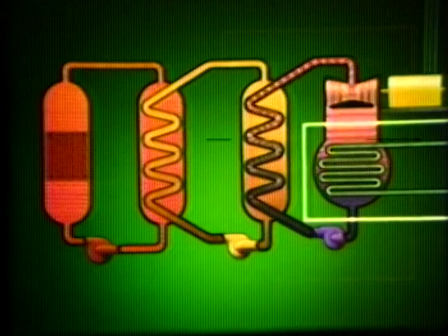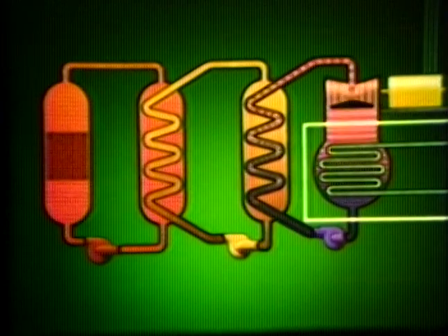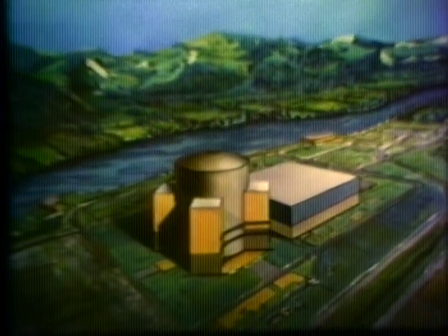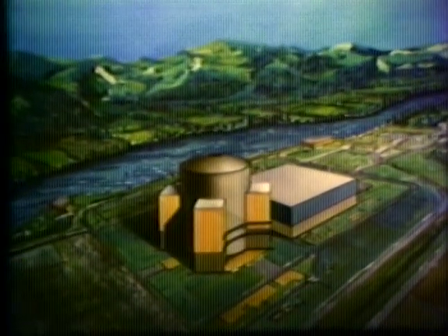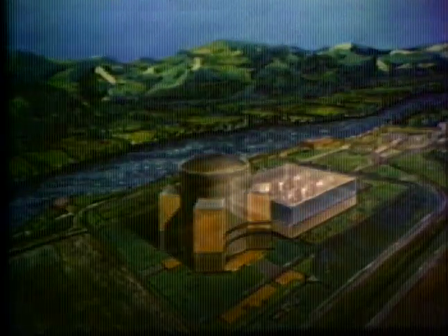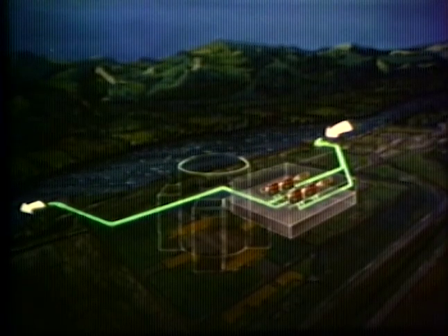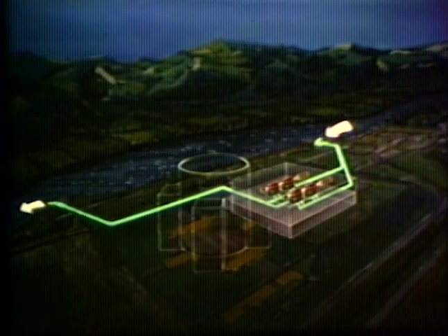Only the 4th system is missing, the condenser cooling system. This system uses water from a nearby river as a heat sink to condense the steam. The water taken in upstream passes under the turbine hall into the condensers and is discharged downstream at a slightly higher temperature. The plant's high efficiency, over 40%, also allows heating of this water to be limited.